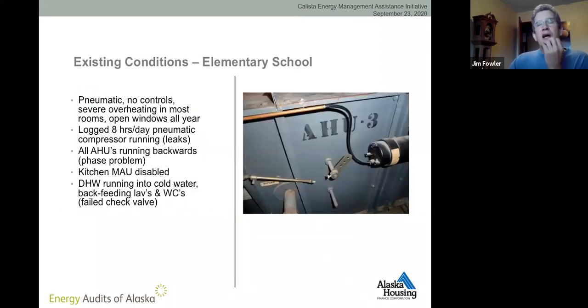This is just kind of a snapshot of some of the things that we found wrong with the school. The controls were pneumatic. There was severe overheating during most of the year. Windows were open, as I mentioned. The pneumatic compressor was running almost continually. All the air handling units, the fans were running backwards. And that was because some electrician came in at some point and switched phases in the main line into the school, main electrical supply. And so all the fans were running backwards.